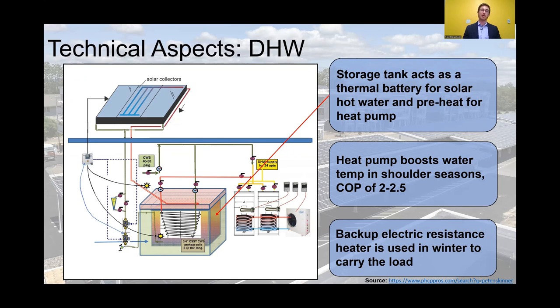So the water comes down and heats up this hot tub through a heat exchanger and then goes back up to the solar collectors and around and around and around until the water gets hot. You then have cold city water going into the hot tub, running through a heat exchanger, and it heats up to the temperature of the hot tub. In the summertime, this can get to 120 degrees and it's ready to be pumped out to the domestic hot water supply. In the shoulder seasons, it needs a little boost.